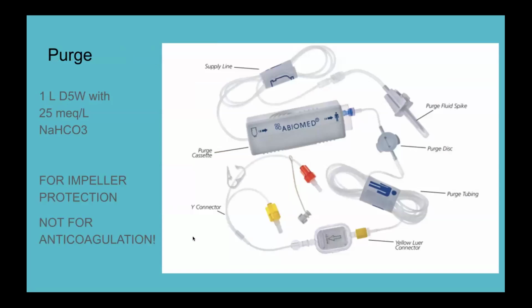I mentioned the purge, and I bring it up only because it's something you need to be aware of. The purge is essentially a continuous flow of fluid. At this point, the fluid is almost universally dextrose with a small amount of bicarb. This is continuously flowing through the device and being dripped onto the metallic part that's actually spinning. The purpose of this is to protect the impeller and avoid blood contacting the metallic surfaces. Again, this used to contain heparin, but it no longer does.